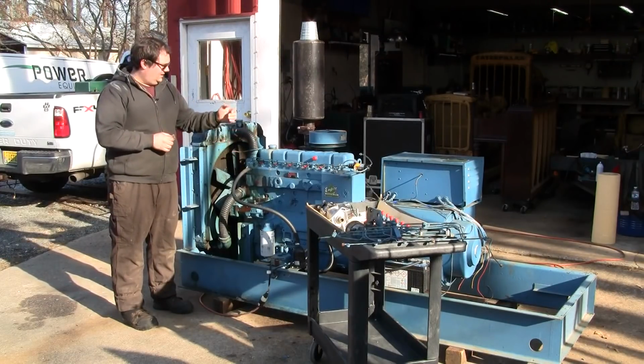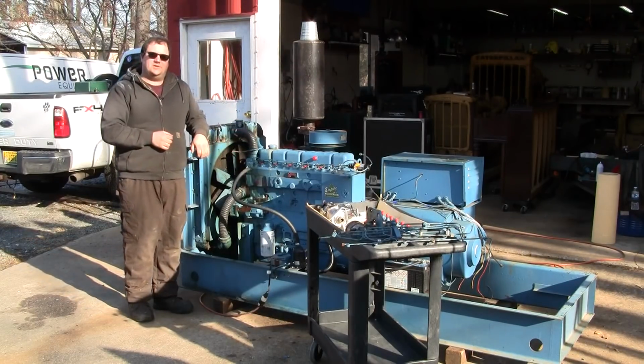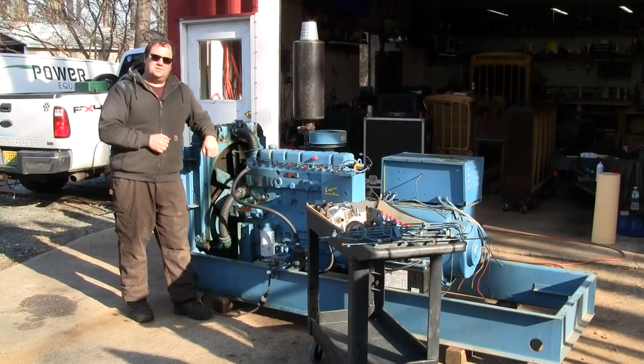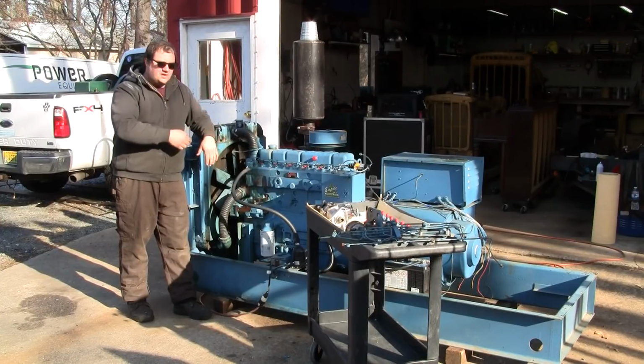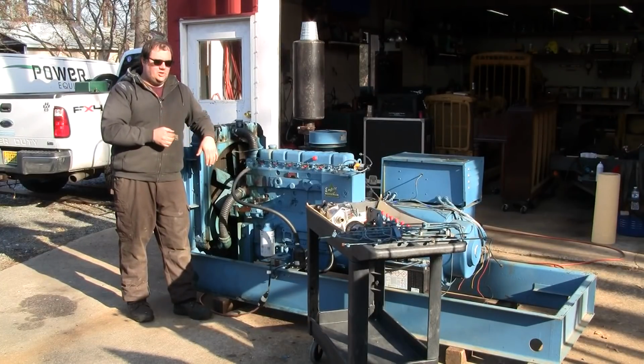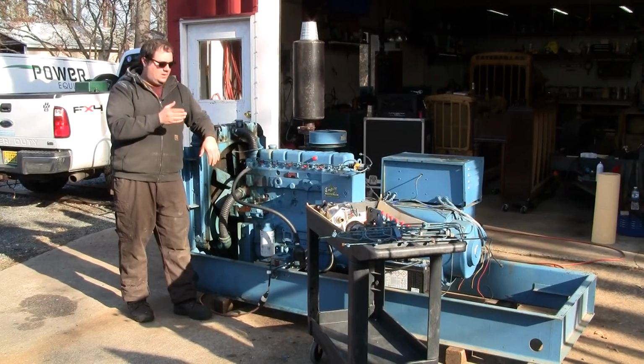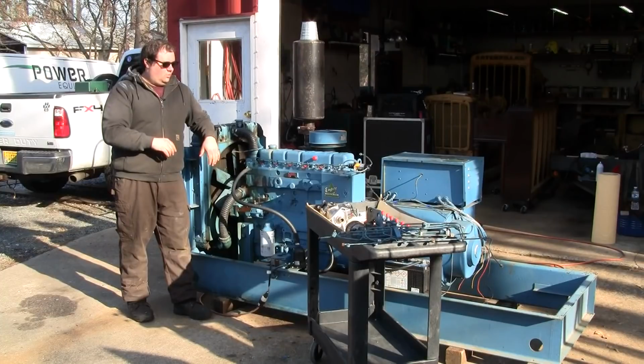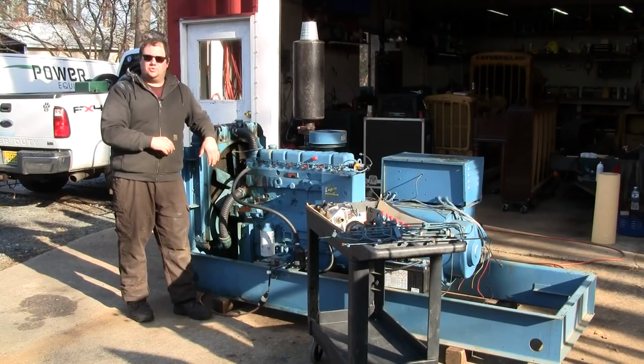We've got the 354 series Perkins on the 45 kilowatt Empire generator set. The job today is to get all the fuel system components reinstalled, hook it up to the load bank, and see if we've got any improvement in engine performance, specifically governor droop. I want this thing to have 1 to 1.5 cycles of droop max. So let's get to it.